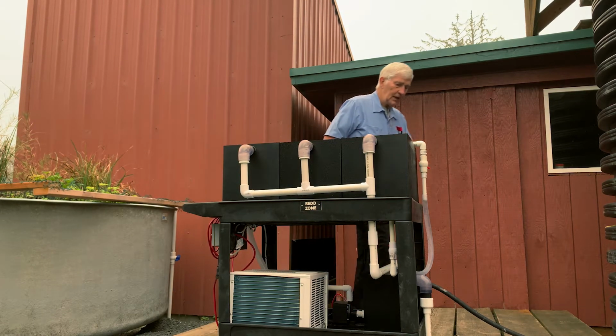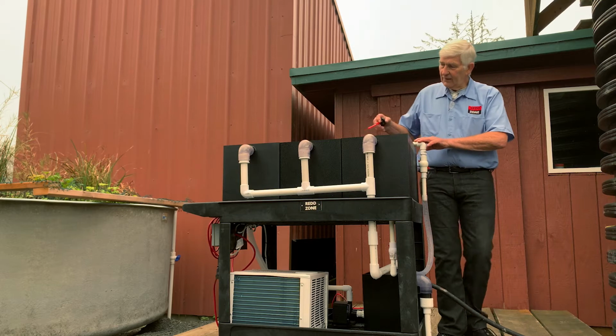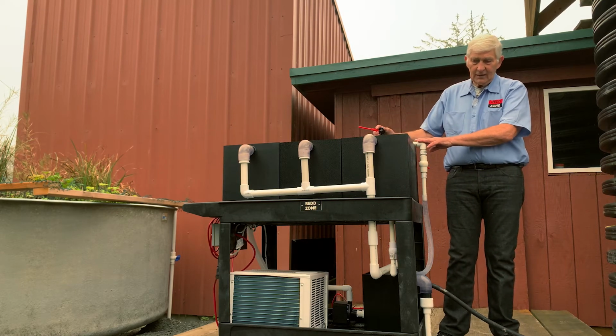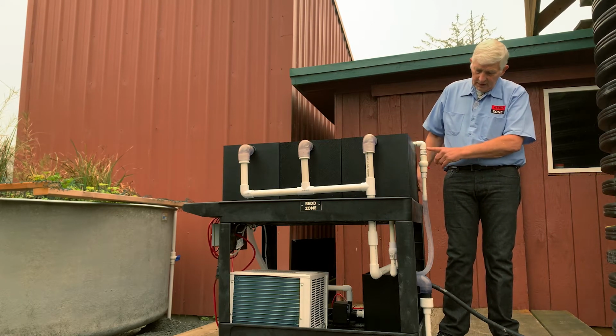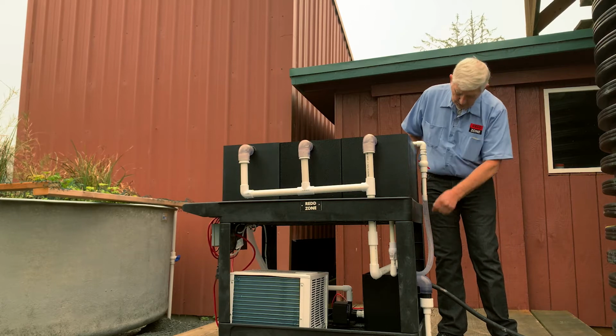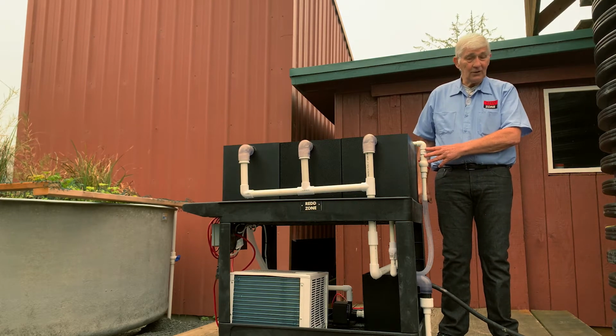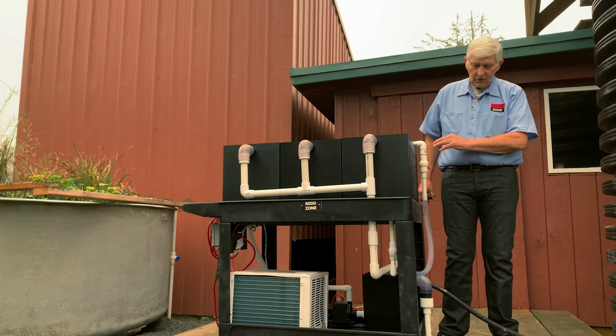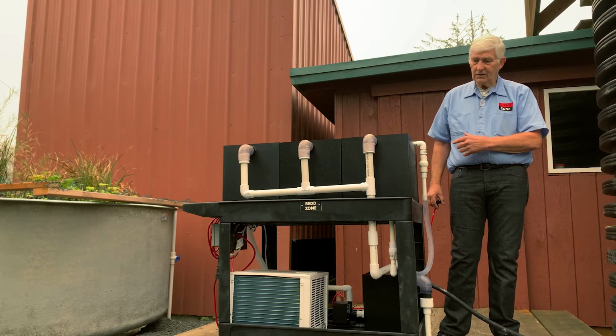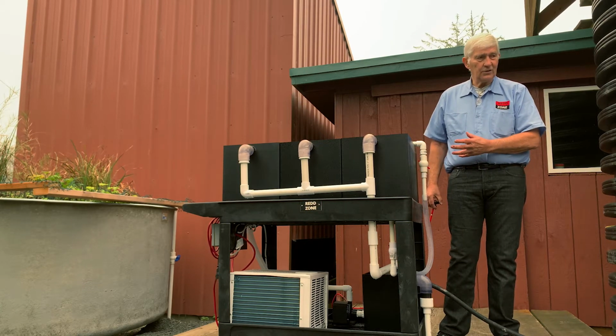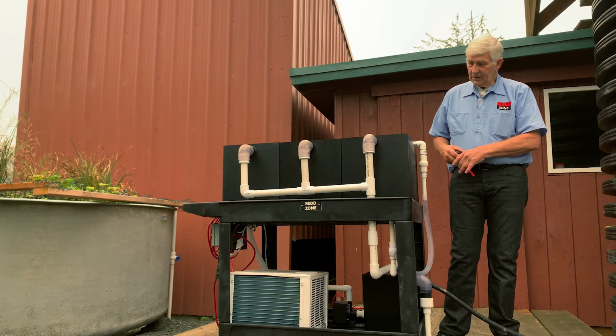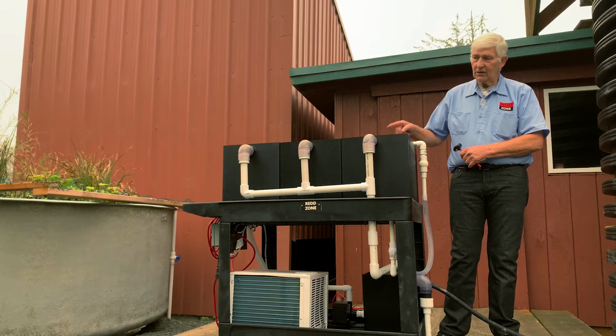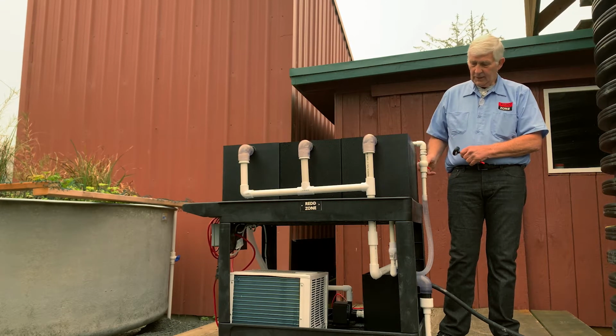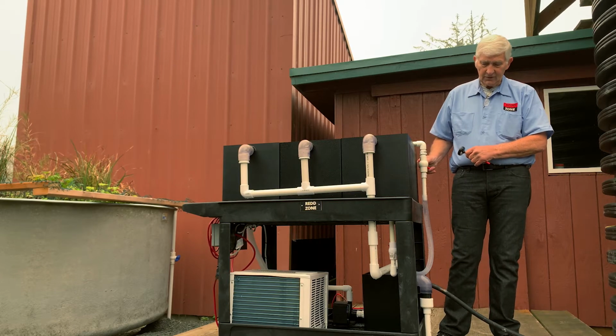On this side we have, in addition to the 5 gallons a minute, about 15 gallons a minute going through the system. We have a bypass line here that runs approximately another 5 gallons a minute. So our aquarium pump that runs the system runs at a continuous 20 gallons a minute. And we simply can control how much of that goes through the incubators by opening or closing the bypass valve.